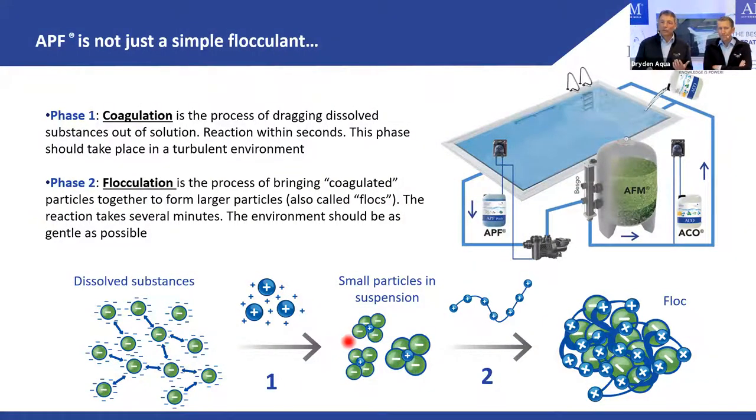Then flocculation uses fishing-net-like long-chain molecules — polyelectrolytes — which go through the water and gather these colloids into a big floc that's very easy to filter. The reaction time is different: coagulation happens within seconds and needs a very turbulent, aggressive mixing environment.